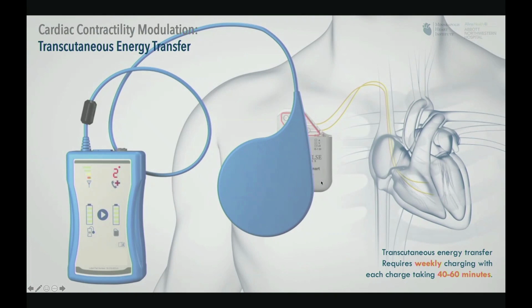Importantly, the device is powered through transcutaneous energy transfer through an inductive coil that has to be charged for 40 to 60 minutes weekly. And the device doesn't continuously provide these signals. It gives 5 non-continuous hours of CCM therapy timed usually overnight.